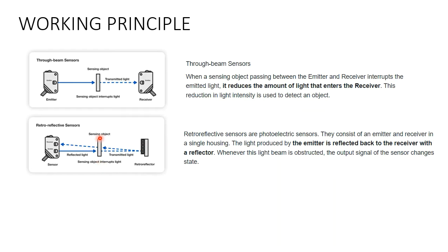When we insert a part in between, the light produced by the emitter would normally be reflected back to the receiver via the reflector. When the light beam is obstructed, the output signal of the sensor changes its state. Initially the receiver is receiving light from the retro reflector, but now it is interrupted, so the signal is sent — and that's how the retro reflective sensor works.